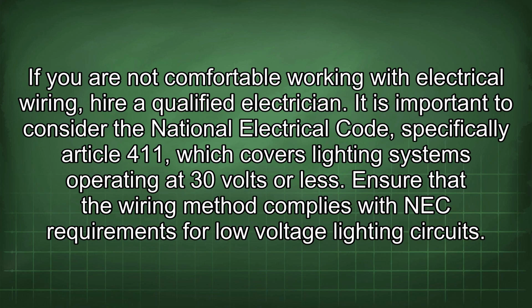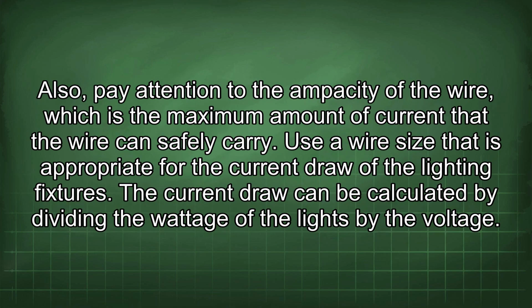It is important to consider the National Electrical Code, specifically Article 411, which covers lighting systems operating at 30 volts or less. Ensure that the wiring method complies with NEC requirements for low voltage lighting circuits. Also, pay attention to the ampacity of the wire, which is the maximum amount of current that the wire can safely carry. Use a wire size that is appropriate for the current draw of the lighting fixtures.